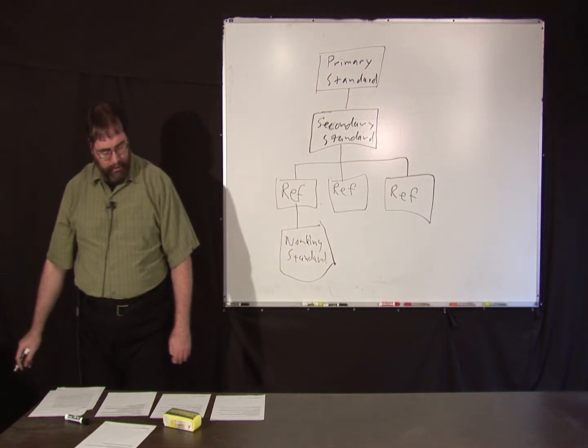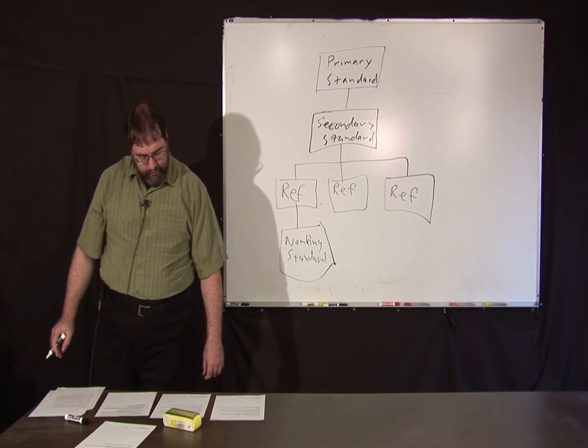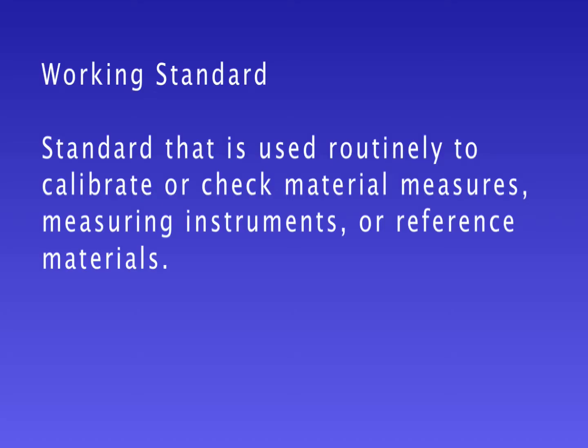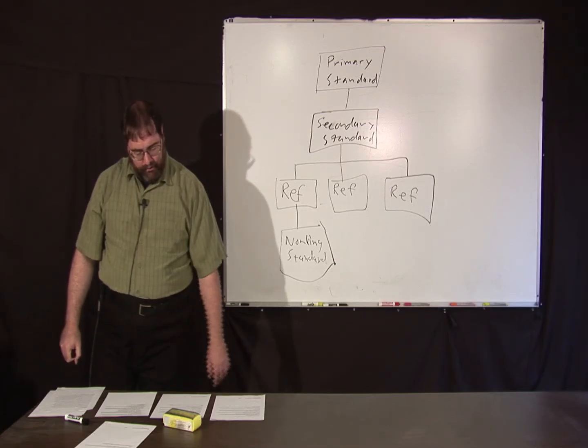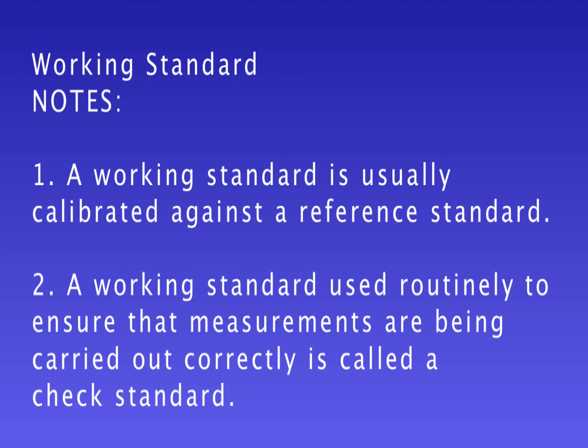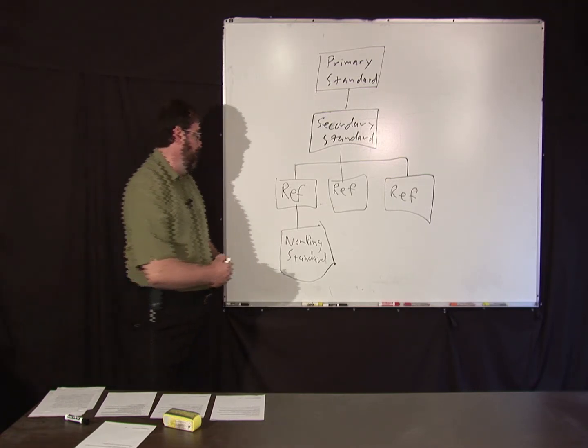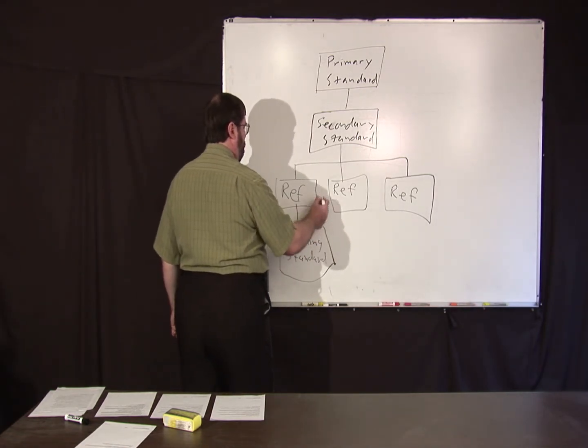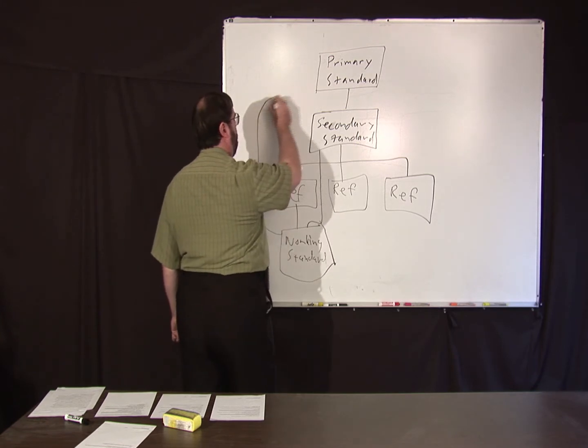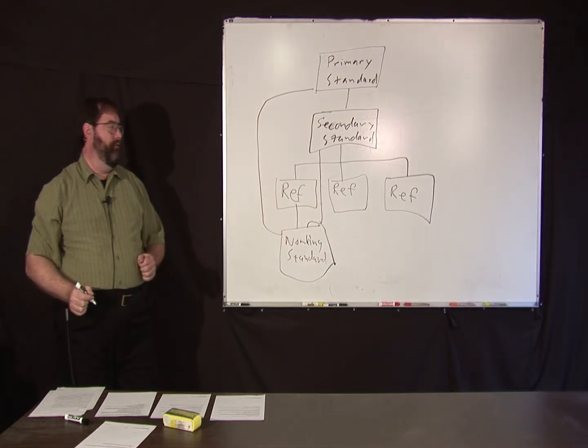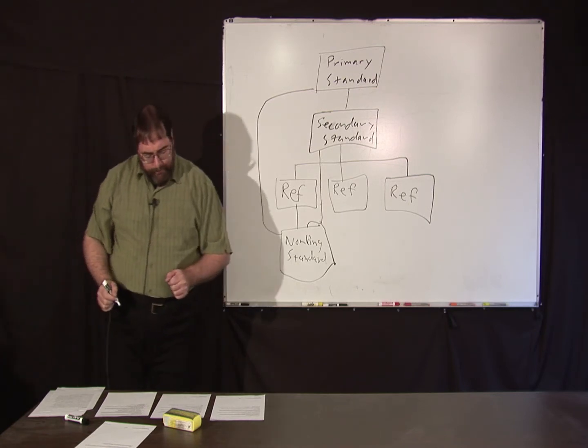Working standards are defined in the VIM as a standard that is used routinely to calibrate or check material measures, measuring instruments, or reference materials. A working standard is usually calibrated against a reference standard. A working standard that is used routinely to ensure that measurements are being carried out correctly is called a check standard. So, a check standard is something just to make sure that your process is working correctly. It could be that a working standard, if the accuracy requirements are such, it might be calibrated against a secondary standard or a primary standard, but you generally wouldn't do that unless you absolutely had to.